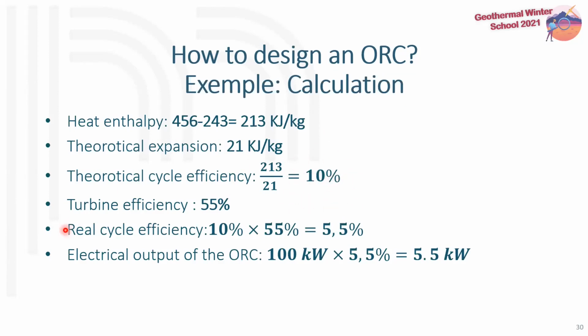We get 10% for the theoretical efficiency. We know that our hypothesis for the turbine efficiency is 55%, so the real cycle efficiency must be 10% multiplied by 55%, and we get 5.5%. So the electrical output of the ORC will be 5.5 kilowatts.